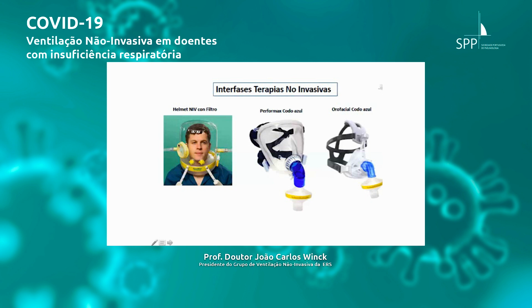CPAP. If you want to use this system and you want to measure tidal volume, you have to add a very small amount of pressure support above the PEEP to compensate for the valve. For example, if you use 10 of CPAP, you can use 5 of pressure support just to compensate for the additional work the patient is doing for the valve. So if you use the helmet, this would be the setup with a filter, and if you use a total face mask, so the Perform Max or the Fit Life, you also need.